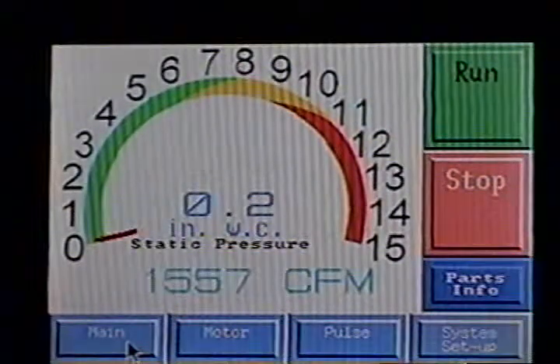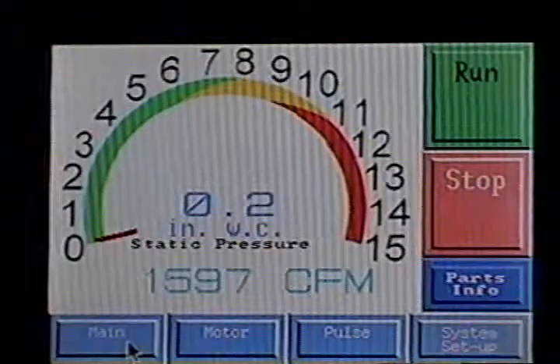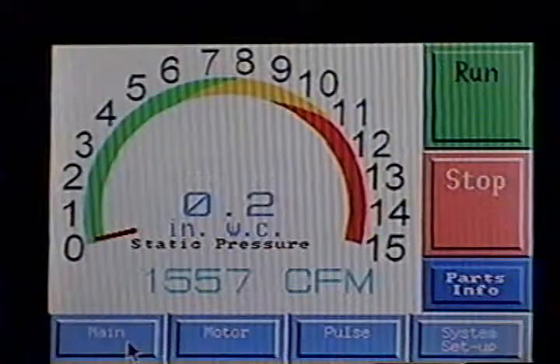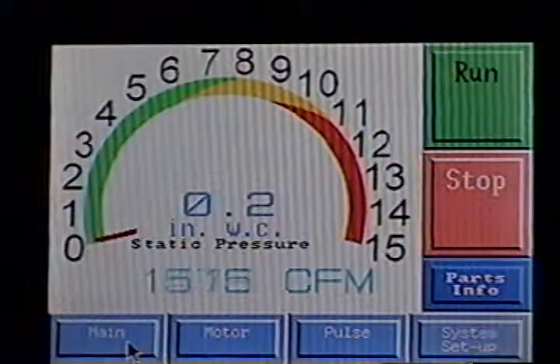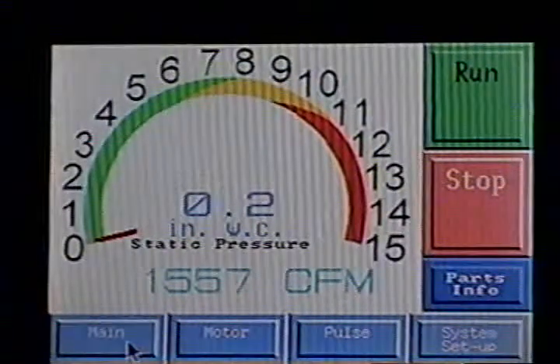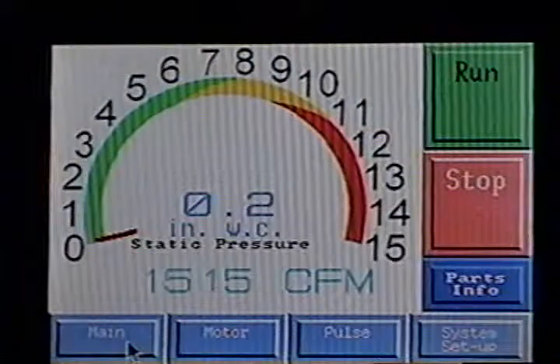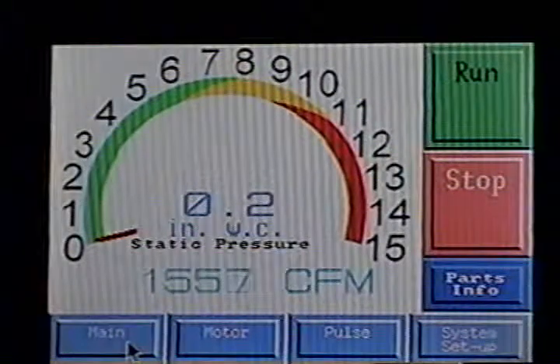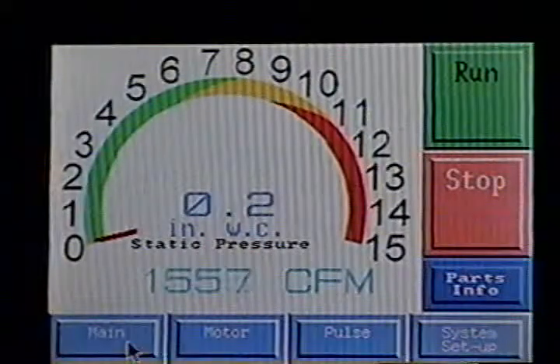We're working our way back down to 1500 because that's why I changed it. It's that simple to go in and set up your system for the CFM you want. You now don't have the motor running too fast, sucking too much air, harming your filters as you're starting up the collector. You have the CFM you want from day one. Go ahead and shut it off.